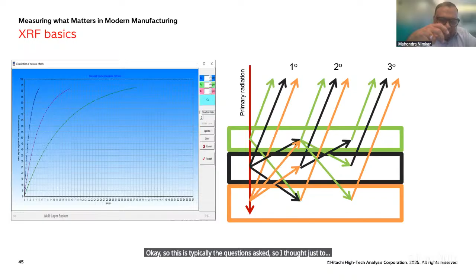Here, if you see the software screen, copper is the base. Then on top there is a nickel layer, then palladium, and then gold. People generally say, my gold is, let's say, flash gold, then Pd, then Ni, and I cannot see the nickel layer properly. These are the kind of complaints or application issues that come up. What happens is, if your top layer element absorbs a lot of X-rays, the reflection from the nickel, for example, will get absorbed in the gold layer itself, or maybe in the palladium layer itself. The X-rays reflecting from nickel will not reach the detector.